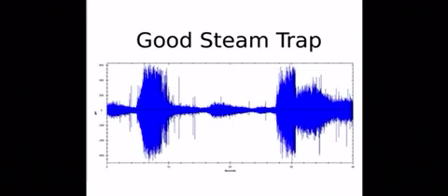Look at the dynamic time signal of a steam trap that's functioning properly. Here you can see it. It's opening here, it's purging, it's closing, it opens again, and then it's purging again. Very simple. A valve with an IQ of 1.